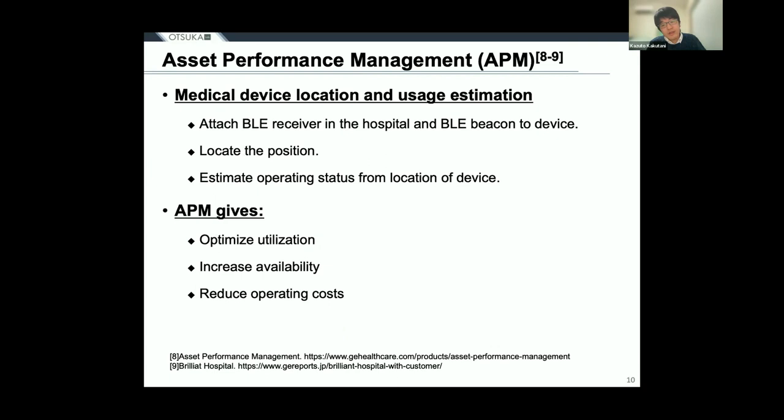Next, I would like to introduce a system called Asset Performance Management, provided by GE Healthcare, as a method for collecting the location and operating status of medical devices. APM is used in factories and hospitals to optimize equipment performance. Multiple BLE receivers are installed at various locations, and BLE beacons are attached to medical devices to locate them. Based on the measured position, the system calculates the time the medical device spends at each location and determines their operating status and uptime. APM solutions give data-driven insight to help optimize utilization, increase availability, and reduce operating costs of healthcare equipment.